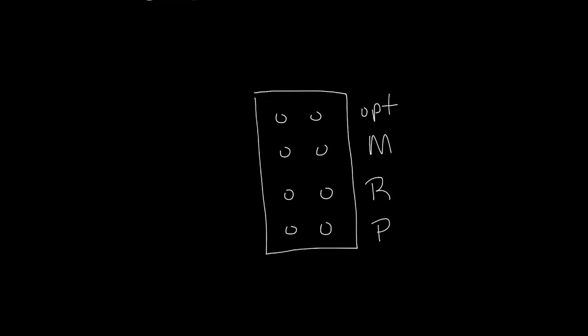Some remote PWMs also include additional features. Some provide a manual speed adjustment that can be used for balancing prior to commissioning the VAV controls. It may also be possible to add a jumper to temporarily or permanently convert a remote PWM into a manual PWM. It may also be possible to add a jumper that enables the 0 to 10 volt DC speed signal to turn the motor off at voltages less than 2 volts DC.